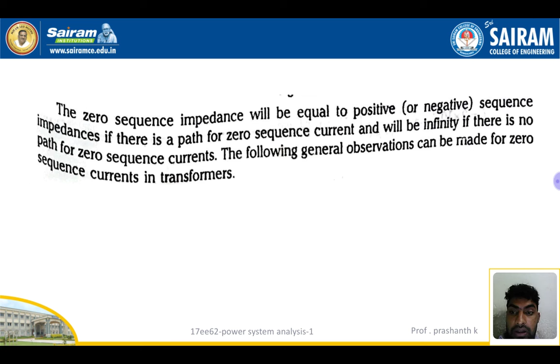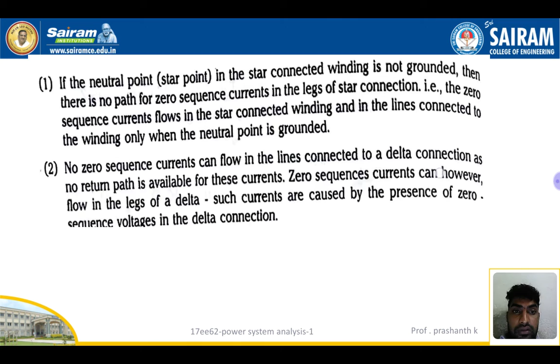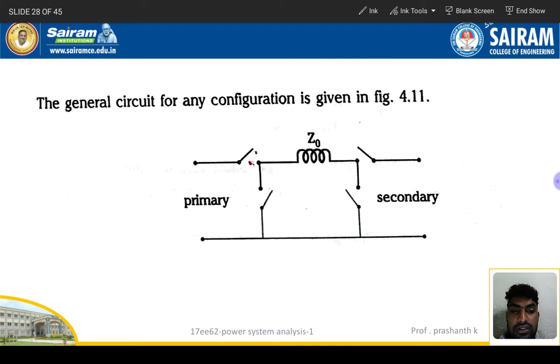Just as an example, if the neutral point is not there versus if the neutral point is there, with or without impedance, it is considered accordingly. It also depends on whether it is star or delta connected. So this is the general circuit configuration of the transformer, showing the zero sequence impedance, and these are the diagrams for configuration winding connection in the zero sequence network.